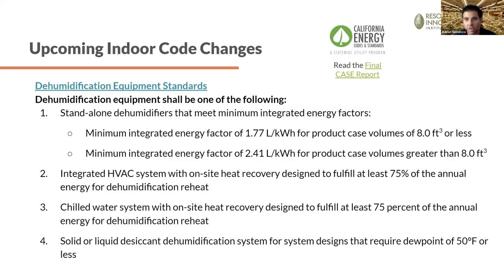The main highlights here are: if you're going to use HVAC integrated type systems, chilled water systems, similar to what Brian was just talking about, we basically need to be reusing and recovering heat that was generated through the process of cooling. We need to reuse that heat for reheat — at least 75% of it has to be generated on site to be reused and reheated. So something like hot gas reheat in a DX system, or heat recovery chillers, like Brian mentioned, in a chilled water hydronic system.